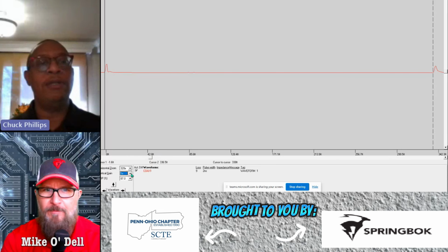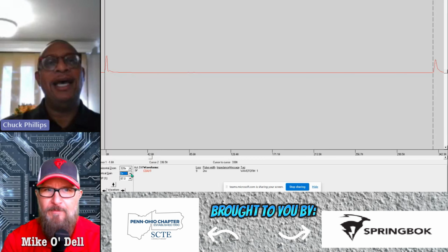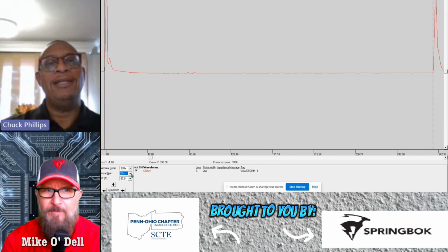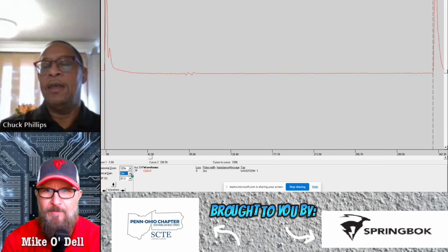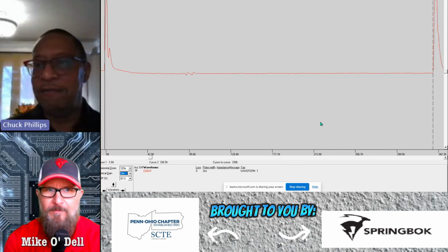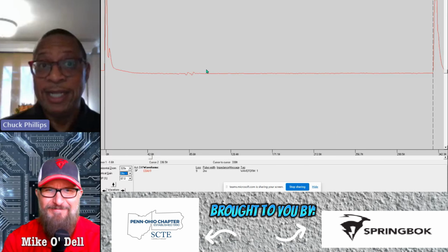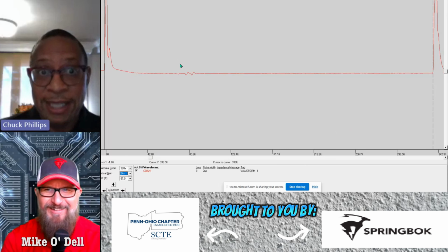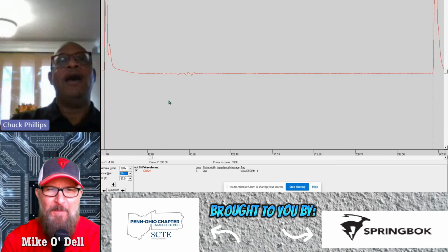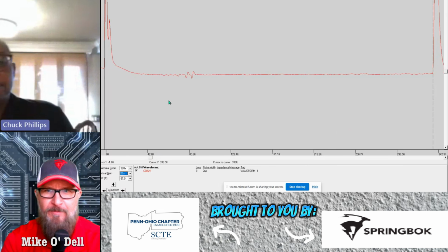So from this point, this is what I'm going to start to do. Remember what I said, most things you're looking for are easy to find? As I just start to increase my vertical gain just a little bit, we can automatically tell where the problem is we're looking for in this cable. It's somewhere right around here. Stevie Wonder can see that. It is fairly obvious that this is the problem, right? So if I just slowly start to increase my vertical gain, here's the deal.